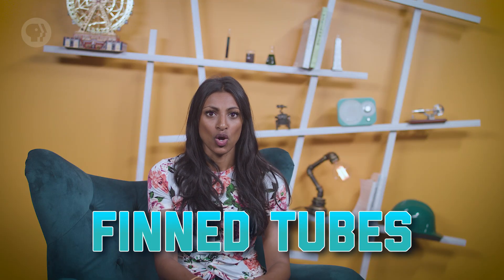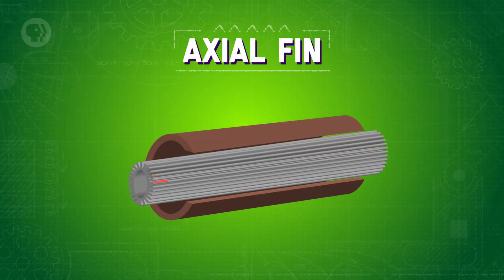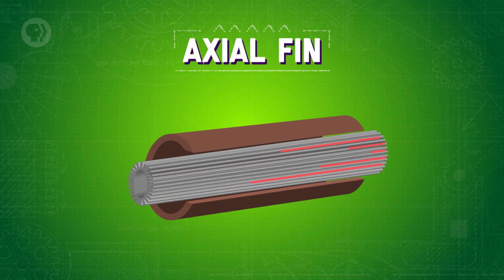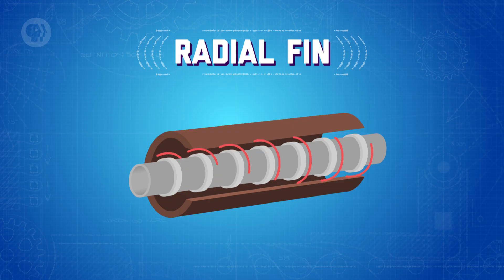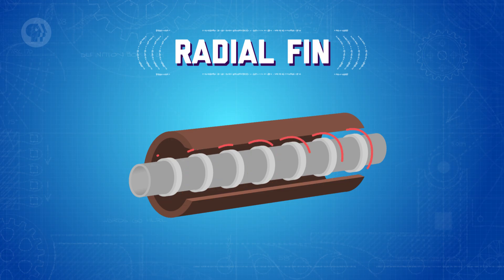So it's worth looking at some other heat exchanger designs. Take fin tubes, for example, which you'll often find in industrial applications like power plants, industrial dryers, and in the air conditioning units of large buildings. In these designs, fins are added to a tube to increase its surface area, which enhances its rate of heat transfer. There are two main types: with axial fin structures, fins run along the tube lengthwise — best suited for slower, more viscous fluid flow, like oil. With radial fin structures, discs are added to the tube and spaced out at regular intervals — best suited for faster-moving fluid, like air, to flow around the tube.